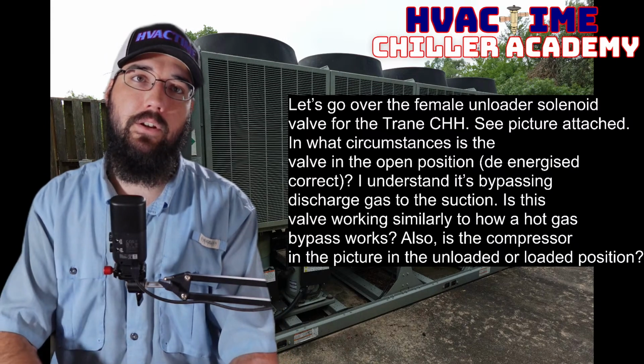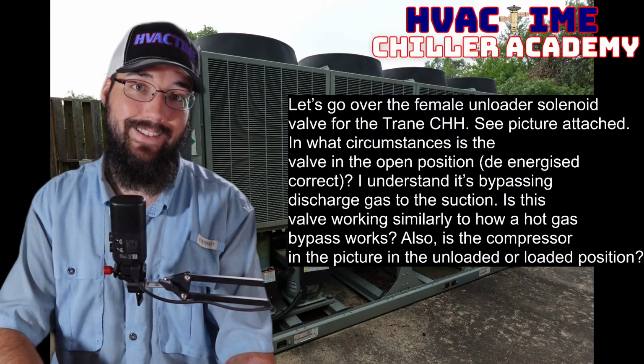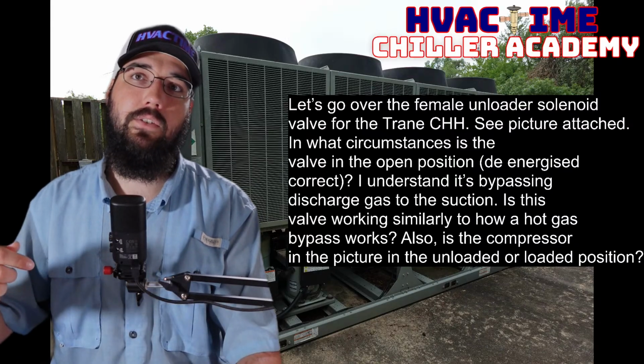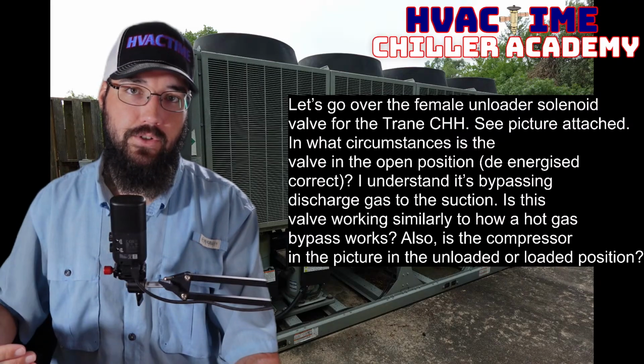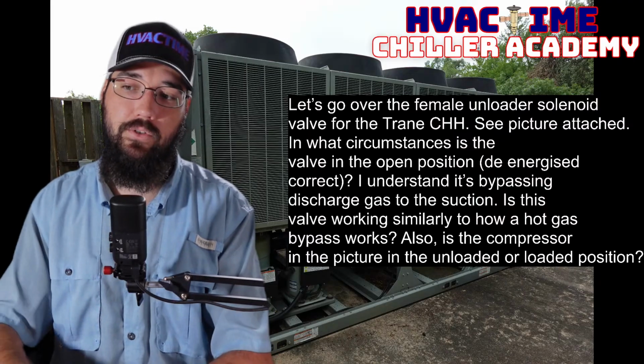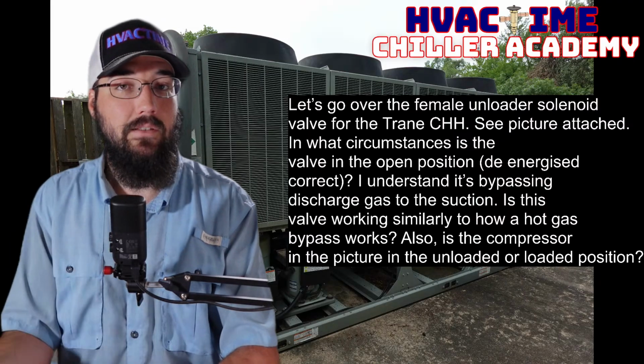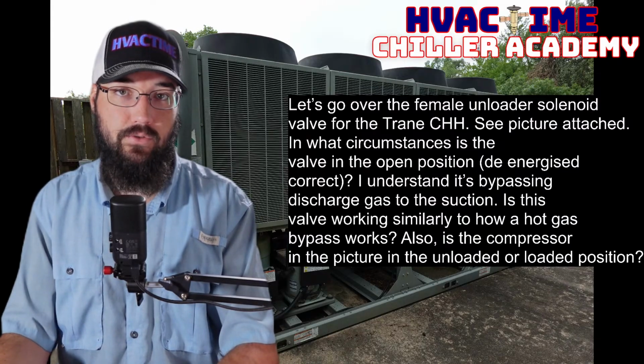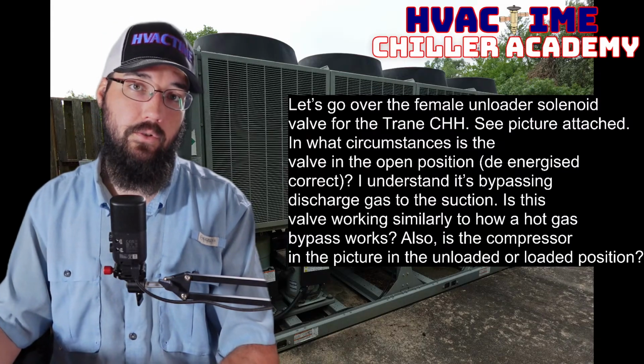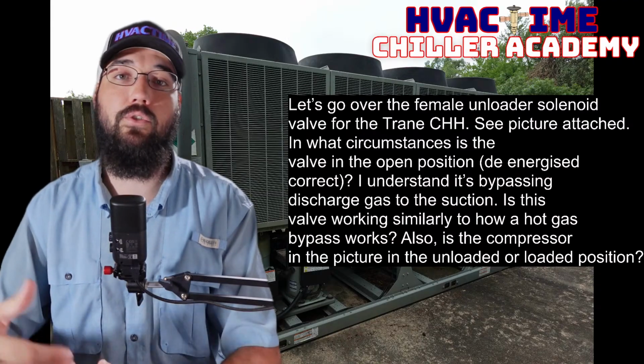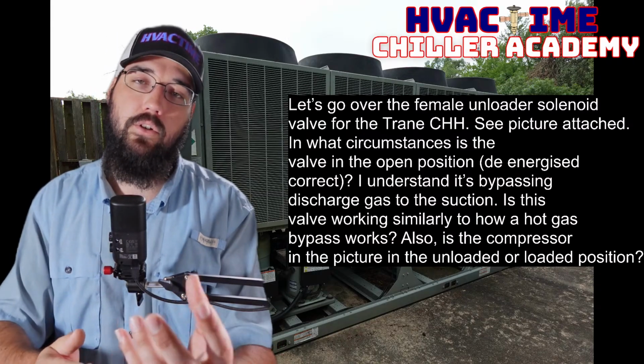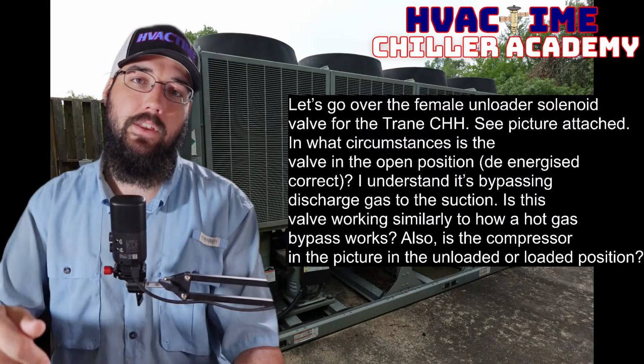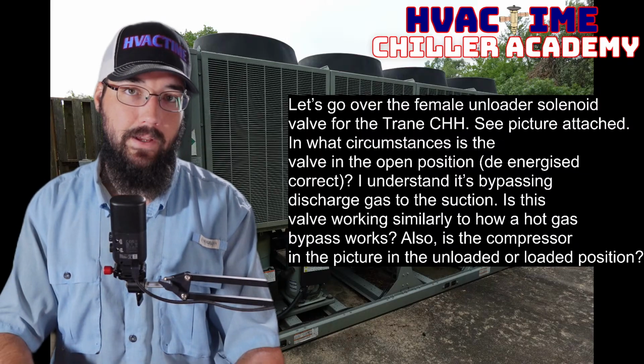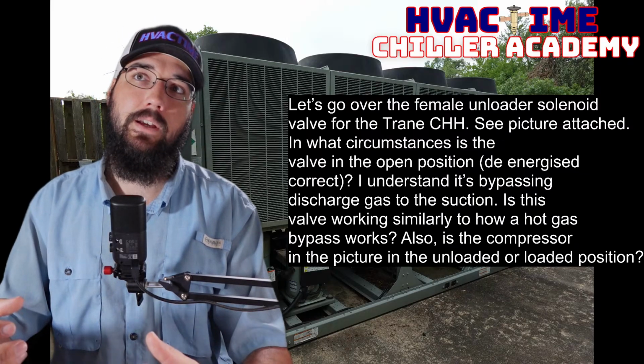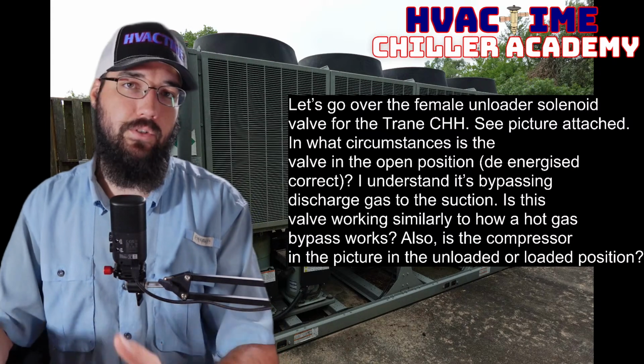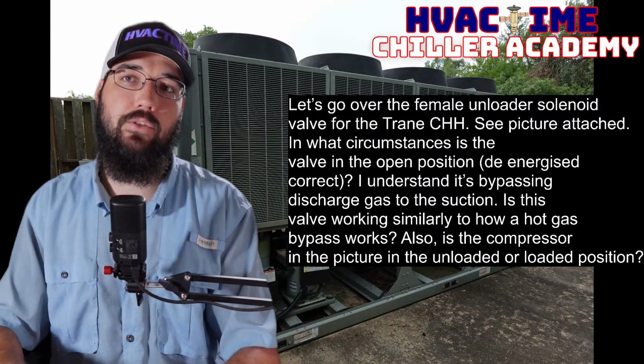And if you hear that the female unloader has engaged, but you didn't hear a sound change in the tone, or the compressor is just struggling to stage up, while there could be a slide valve issue in your male load and unload valve, those could have an issue. You could have an oil issue. You could also have the female unloader that is not closing the internal bypass. And at that point, the compressor is just not going to be able to increase in its staging.